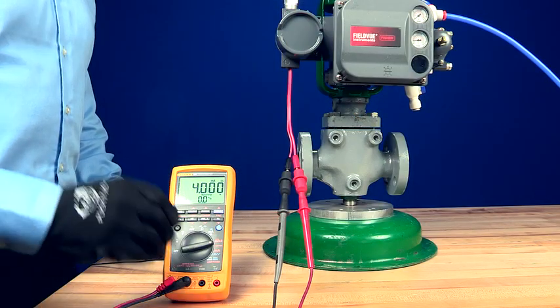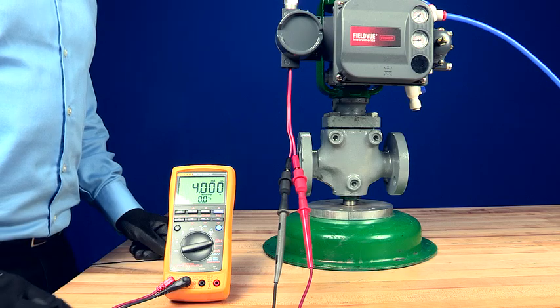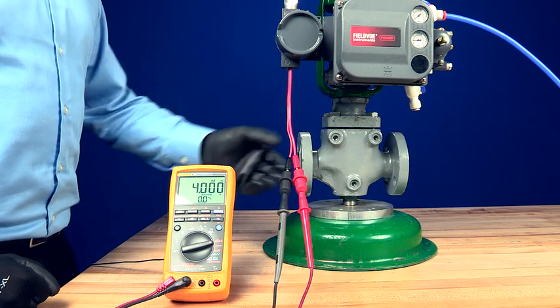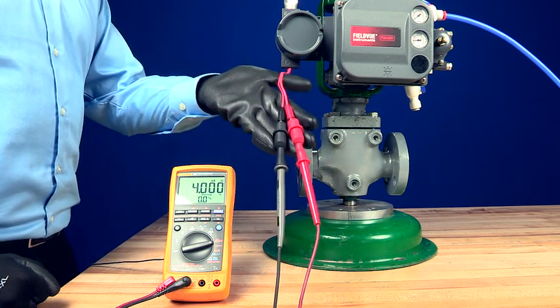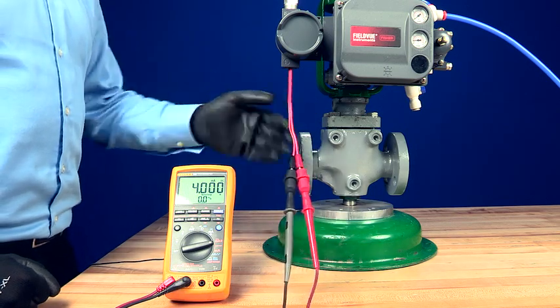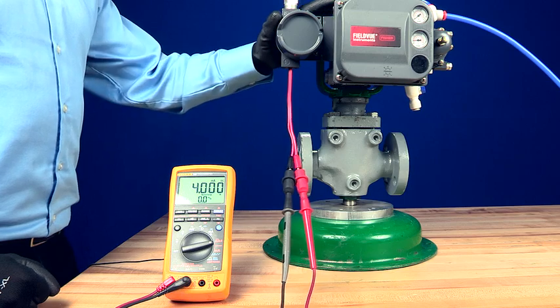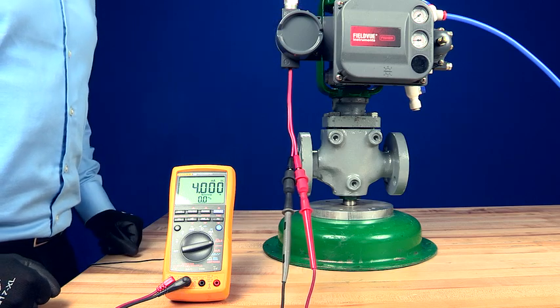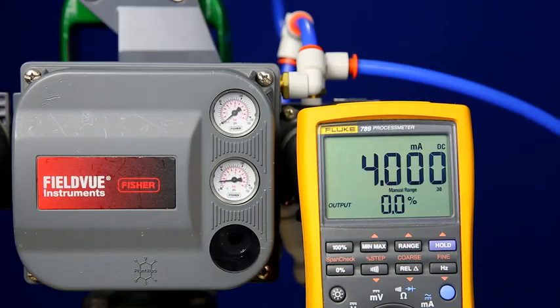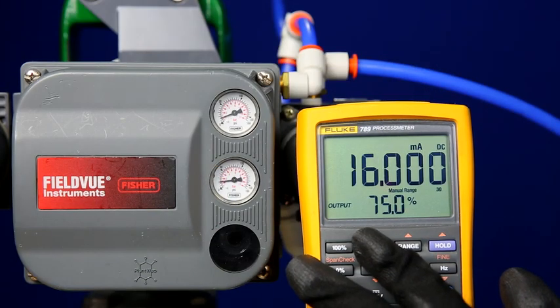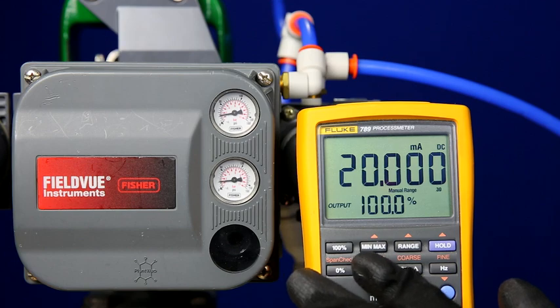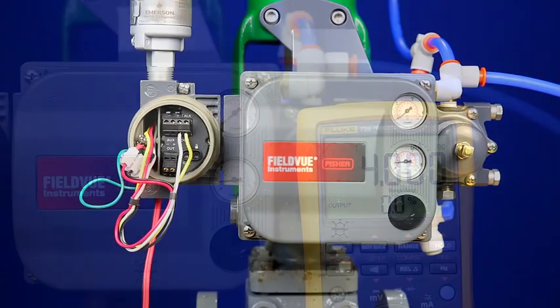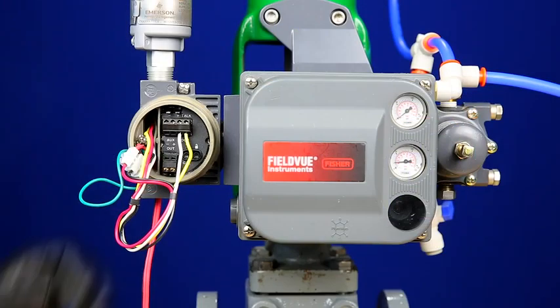simulates the function of an analog output from the control system and provides a 4 to 20 milliamp input signal to the DVC 6200. The signal is processed and converted to pneumatic outputs to control the valve.